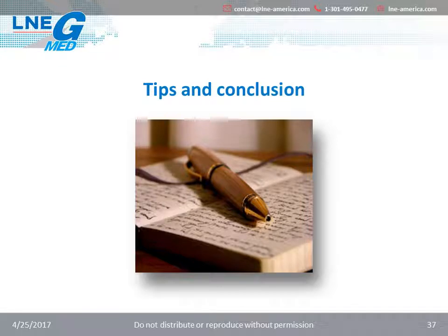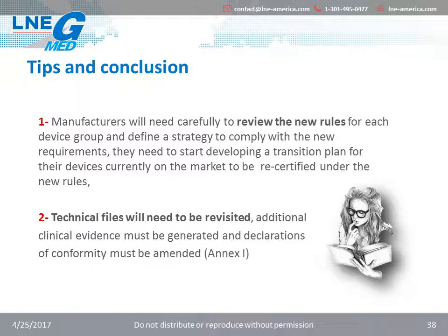We are coming close to the end of the MDR portion of the webinar. I'll try to give some tips and conclusions to the manufacturers. So, number 1 tip, manufacturers will need to carefully review the new rules for each device group and define a strategy to comply with the new requirements. They need to start developing a transition plan for their devices currently on the market to be recertified under the new rules. Number 2, technical files will need to be revisited. Additional clinical evidence must be generated and the declaration of conformity must be amended.